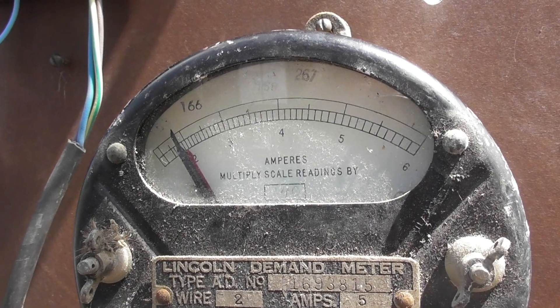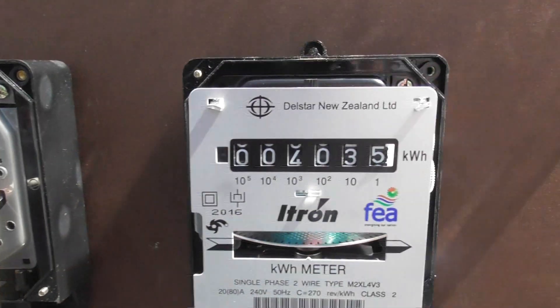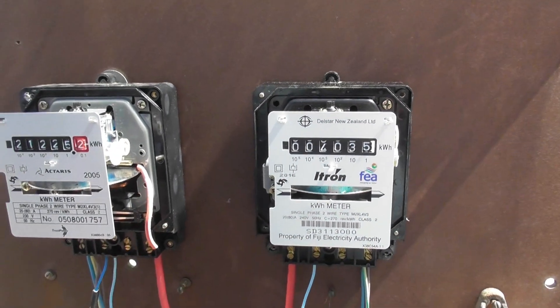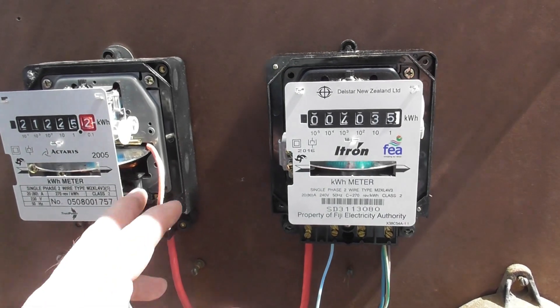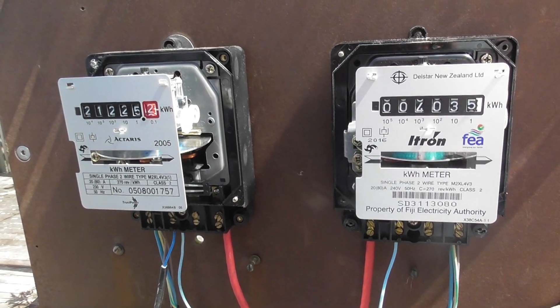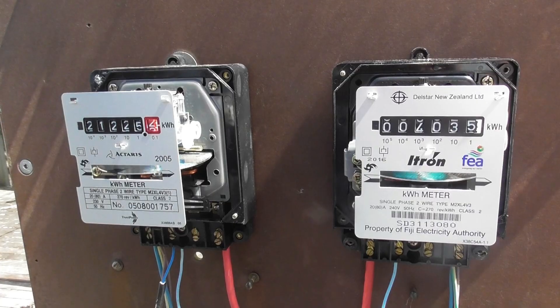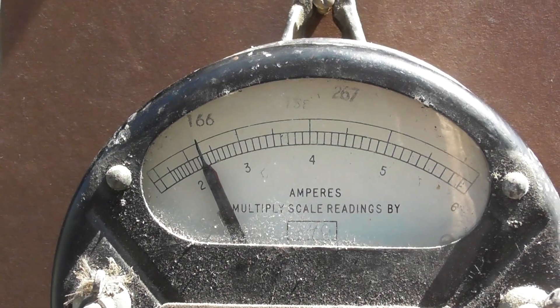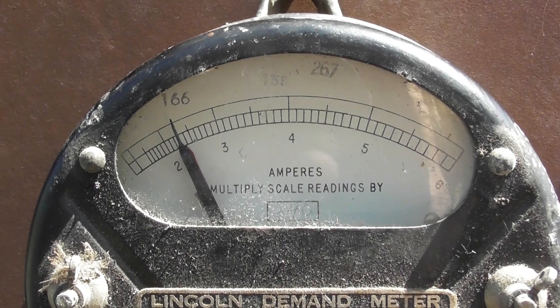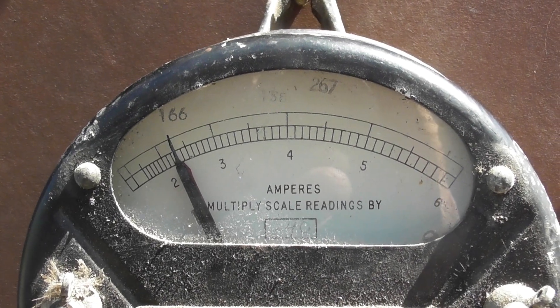The thermal meter has climbed up to 2. I'm going to do the dial test now — reading 21225.2 and 4035, that's on the low end. I'll open the Variac and start this device off. I need to take the brake off here, and we'll see how they go in a run of 10 units — how much difference there is between these meters. The thermal meter is reading about 2.4, so it's reading a little bit low, but these meters have a non-linear scale and are most accurate at a 5 ampere reading, so not too bad.